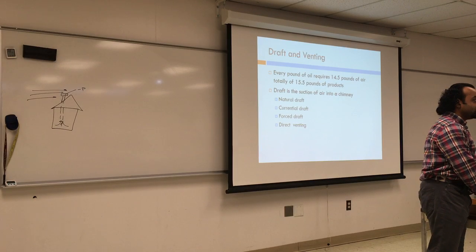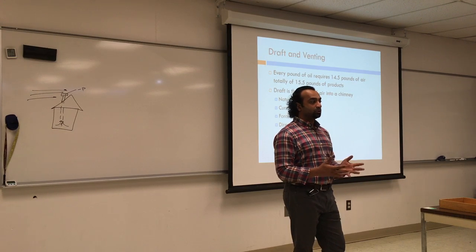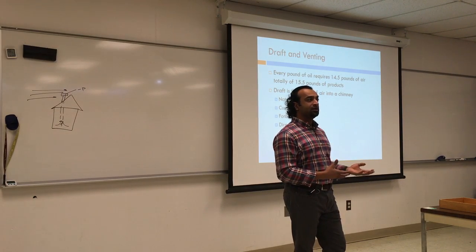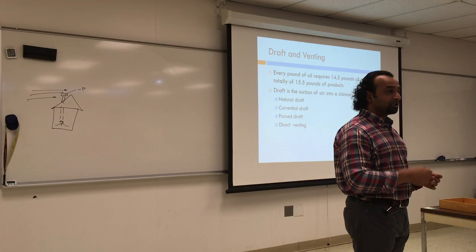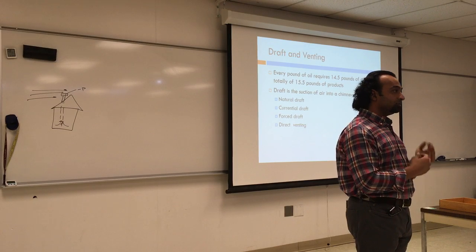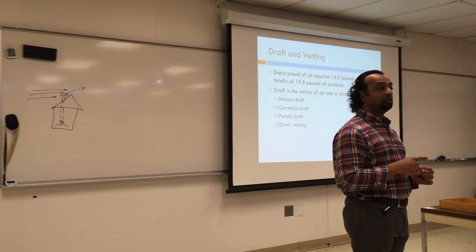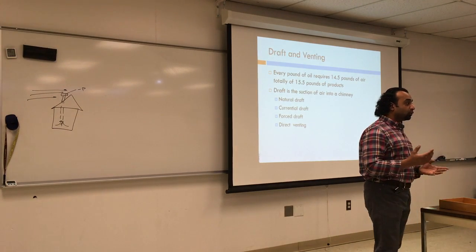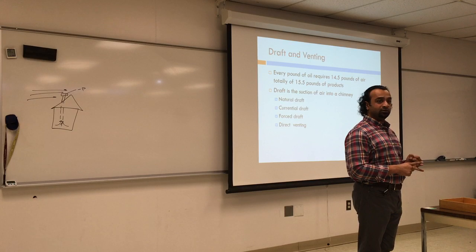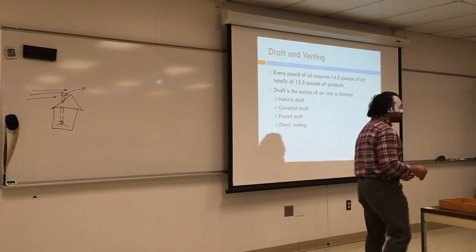That will cause you to have no flame. So again, this is one of the most challenging items to troubleshoot: no flame or delayed flame. Why am I not having flame? I want you to think about the draft as an issue. It could be why you're not having flame or losing flame. There's a sequence of things you have to do to find out why there's no flame. Could be the cad cell has an issue, it's covered, could be the nozzle's clogged, could be the ignition, it could be the draft. So think of all the combustion equation elements, air, fuel, and spark, and see which one is missing, which one is not balanced, and go and check. Eventually, you'll find out.